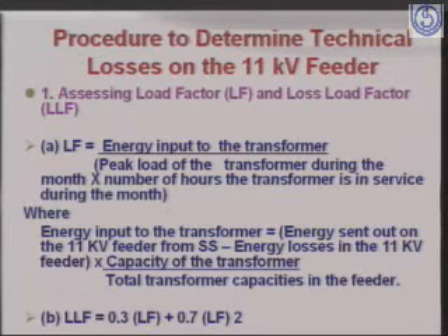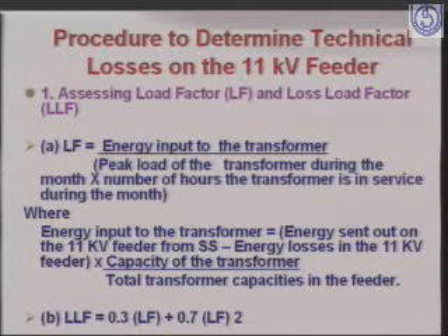During the month, how much maximum demand has been recorded on the transformer, and the number of hours the transformer is in service during the month. Basically this is the load factor. In case we don't have meters, then some estimates are to be made, which are mentioned here: energy sent out on the 11 kV feeder from the substation minus the energy losses in the 11 kV feeder, into the capacity of the transformer, divided by the total transformer capacity in that particular feeder.